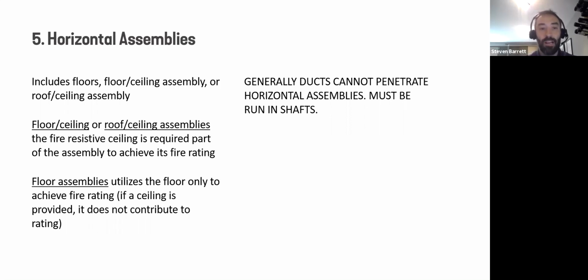But why is it floor ceiling versus floor? You might be wondering what the difference is. The difference is that the ceiling is required. It's actually part of the assembly that helps it achieve its fire rating. Like we saw at the very beginning, we can use gypsum to get fire ratings. So in the case of a floor ceiling or roof ceiling assembly, there's going to be a layer of gypsum, and that gypsum is required. It actually is part of the assembly sandwich, if you will.